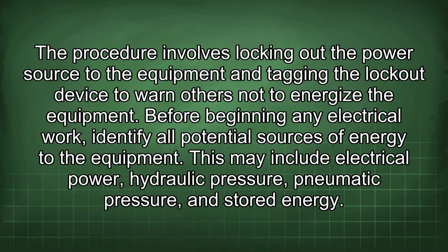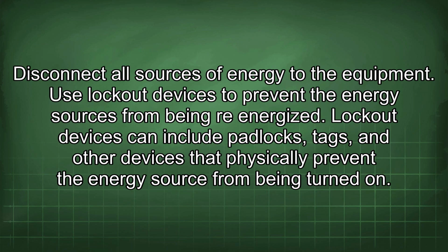Before beginning any electrical work, identify all potential sources of energy to the equipment. This may include electrical power, hydraulic pressure, pneumatic pressure, and stored energy. Disconnect all sources of energy to the equipment. Use lockout devices to prevent the energy sources from being re-energized. Lockout devices can include padlocks, tags, and other devices that physically prevent the energy source from being turned on.